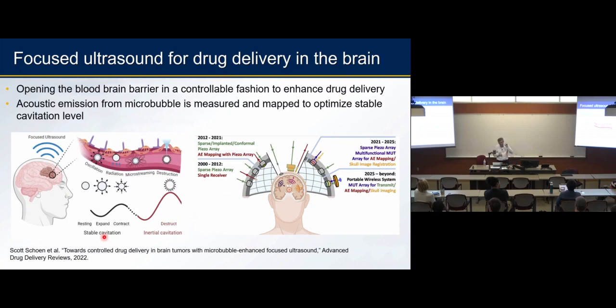And also, at the same time, we're looking at the reflection, so we want to make sure that there are enough microbubbles there, because your signal can go up and down depending on the microbubble density, so you want to calibrate that. So we added that feature to the controller. And so right now, for example, this is being done with piezo arrays, and these acoustic emissions are all done with piezo. We're trying to get into micromachined devices, because in this case, the amount of pressure you need for those microbubbles is not very high. So it may be possible to do all of that using these micromachined devices rather than piezoelectrics. So that will be in the future, maybe a 5 to 10 year time range.